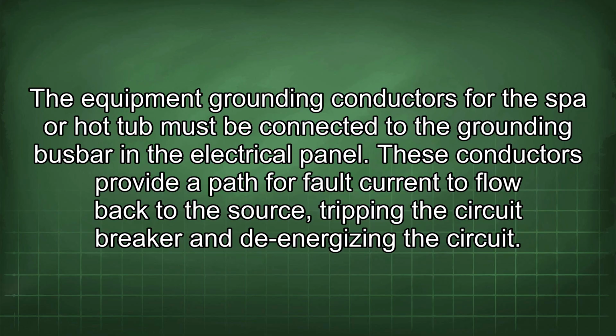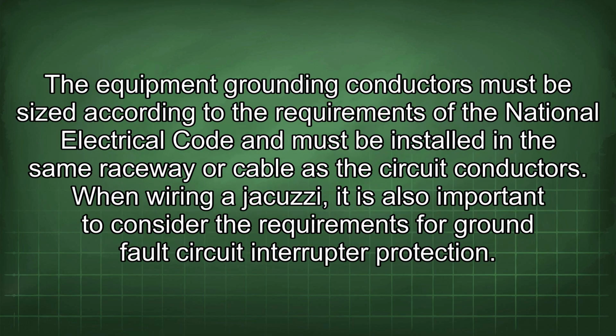The equipment grounding conductors for the spa or hot tub must be connected to the grounding busbar in the electrical panel. These conductors provide a path for fault current to flow back to the source, tripping the circuit breaker and de-energizing the circuit. The equipment grounding conductors must be sized according to the requirements of the National Electrical Code and must be installed in the same raceway or cable as the circuit conductors.